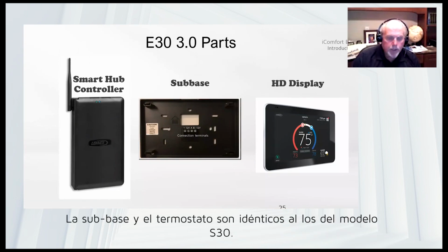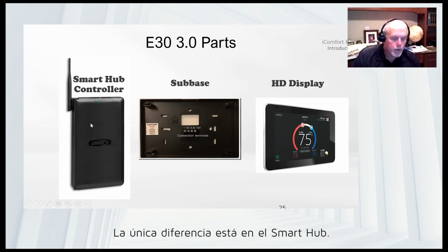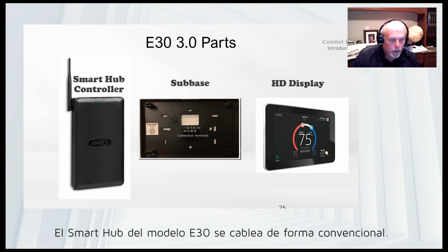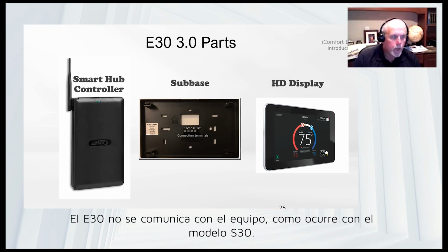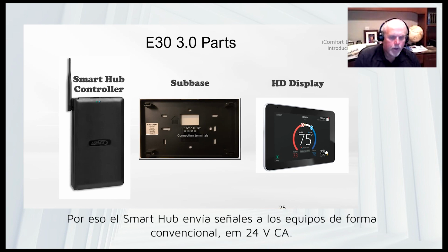Okay, so the subbase and the display are identical parts to the S30. So they are no different. So they can be interchangeable from E30 to S30. The only thing different is your Smart Hub. Okay, the Smart Hub is different with an E30 since we are going to wire conventionally to the equipment. With the E30, we do not communicate directly with the equipment like we do with the S30.